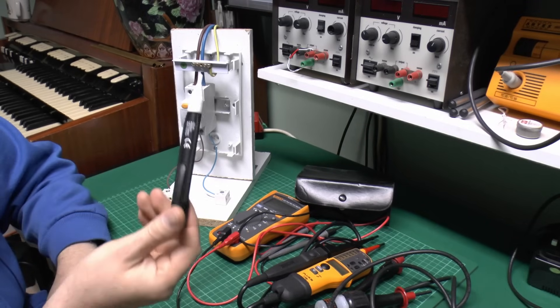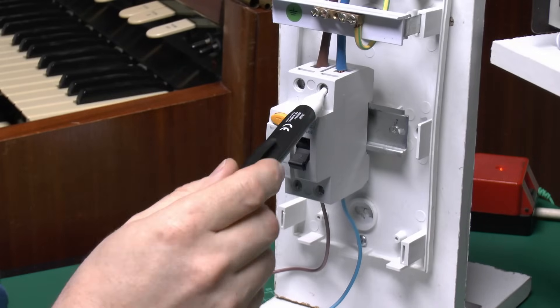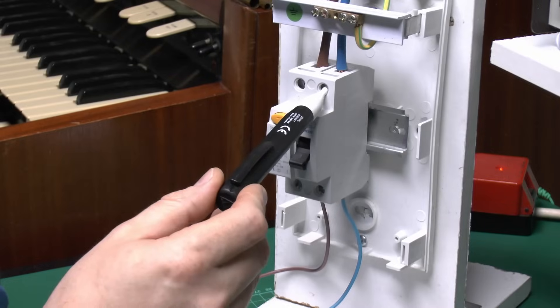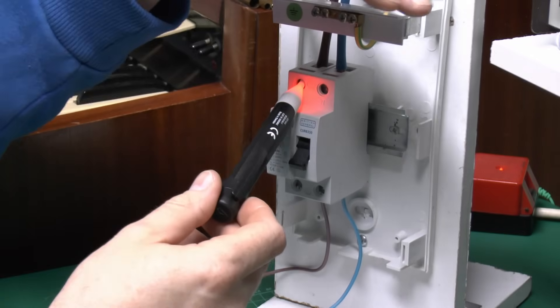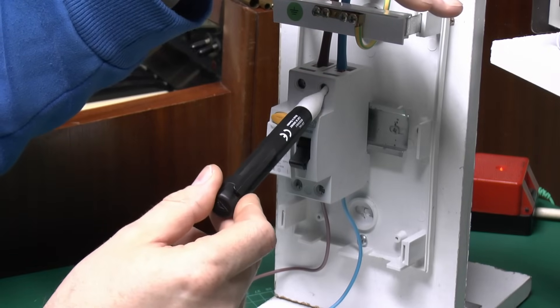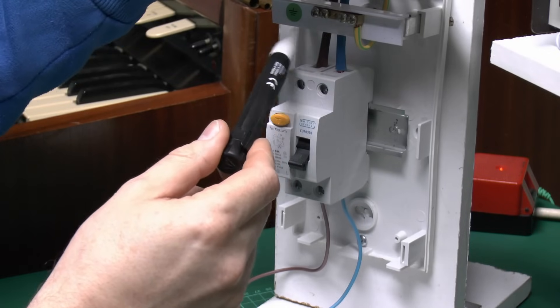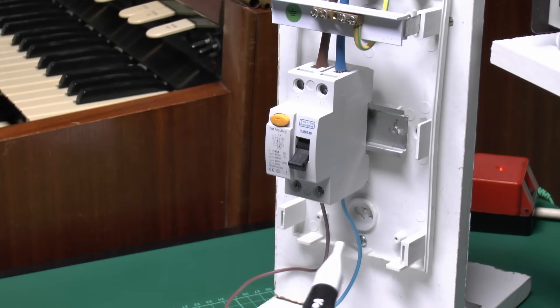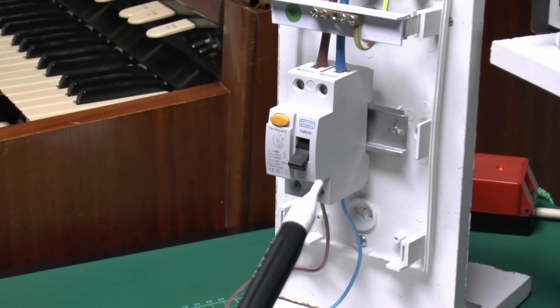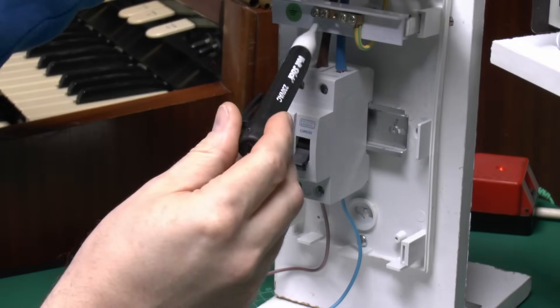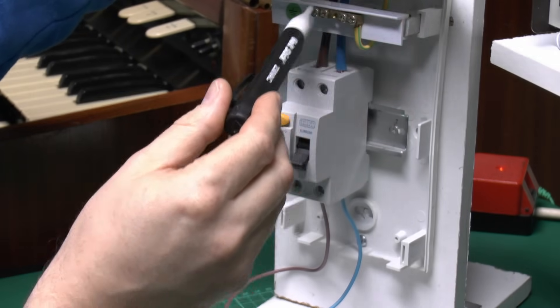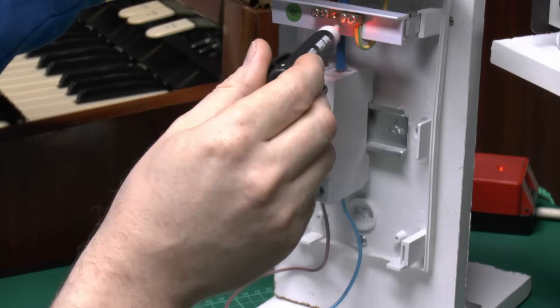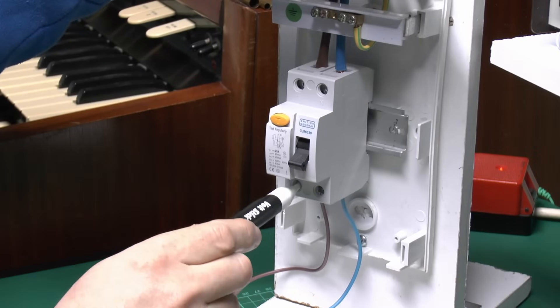Now I've got these devices which are certainly perfectly safe to use. It's all plastic construction, battery powered, just place it on the conductor in question, and if it's connected to the power then it will light up. So of course that's neutral so it doesn't do anything, and I've placed it in the hole there with the line and see it just glows red at the end. But the problem with these is that whilst they can be used to confirm the power is actually on, they're not suitable to confirm that the power is off because again they're not desperately reliable. They're not making any kind of contact with the circuit itself, purely going on a capacitive effect.